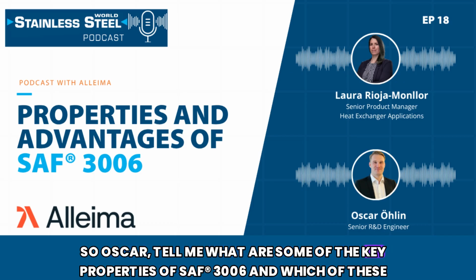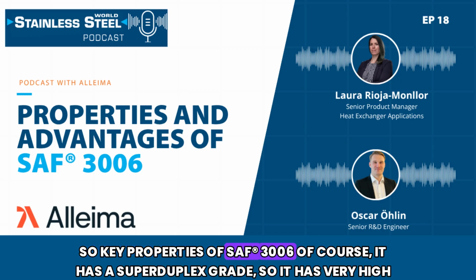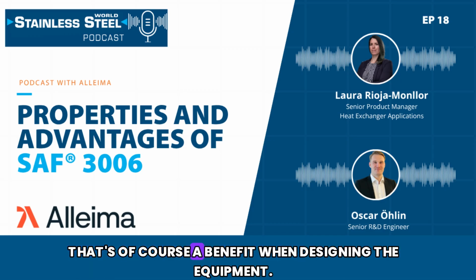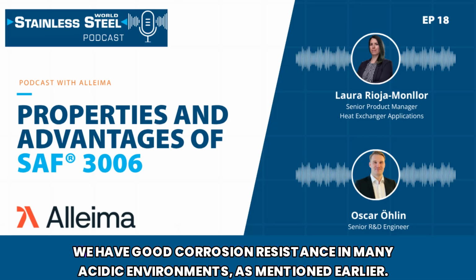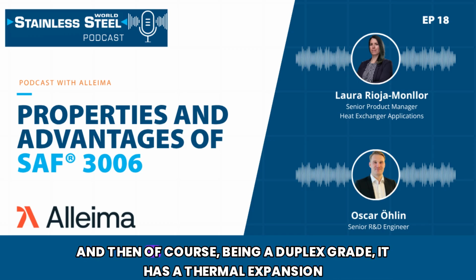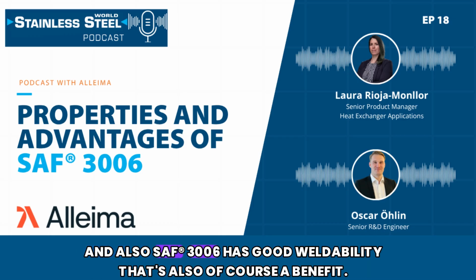Oscar, tell me, what are some of the key properties of SAF 3006, and which of these matter the most for your customers? So, key properties of 3006: of course, it is a duplex grade, so it has very high mechanical strength. That's a benefit when designing the equipment. But I think the most important is the corrosion resistance. We have good corrosion resistance in many acidic environments, as mentioned earlier. And being a duplex grade, it has a thermal expansion similar to carbon steel that can give design advantages when, for instance, fabricating a heat exchanger. And also 3006 has good weldability. That's also a benefit.